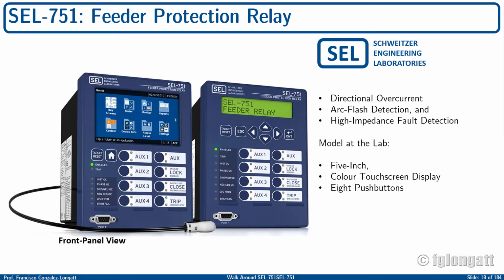Okay. But before we start with the physical and real device explanation, I would like to tell you a bit about this SEL 751 feeder protection relay. This relay is basically a feeder protection, which means that it is intended for use at distribution systems, and this device is able to work with radial configuration or loop distribution configuration. Okay, and the device is equipped with very comprehensive protection capabilities, including, of course, the classical overcurrent, but going beyond that with directional overcurrent, auto reclosing, under voltage, under frequency, cable line thermal, and so on.